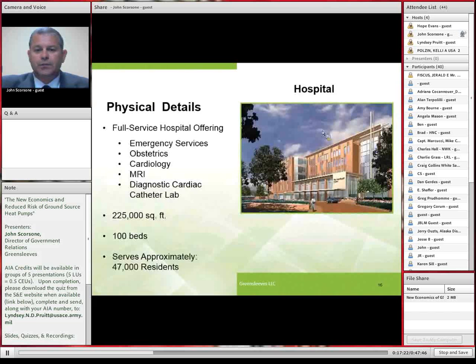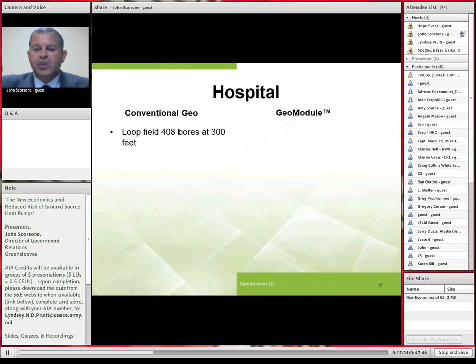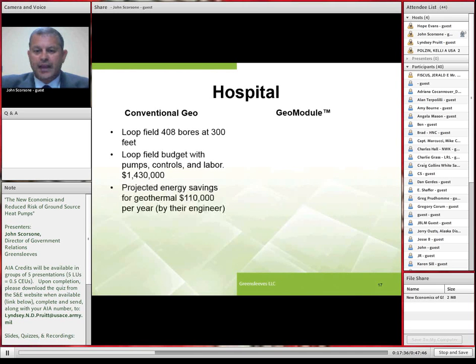But with the Greensleeves GeoModule, the loop field was designed using only 196 bores at 300 feet. Adding the cost of the GeoModule and the fluid cooler that burns off excess heat, it came to just slightly over $1 million. But the fluid cooler requires energy usage, so the net energy savings was $106,500.